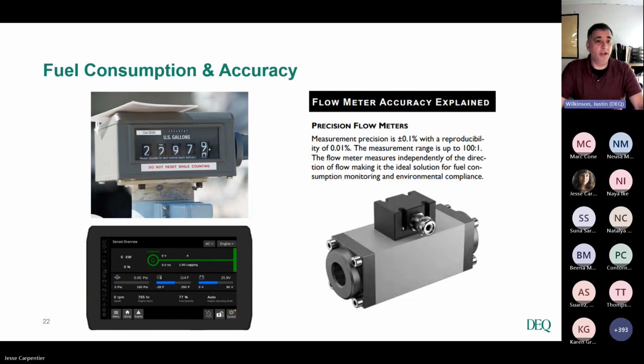When we started to apply that 5% to facilities, that was a huge amount of operation they were losing out on. So facilities started to look into external fuel flow monitors with higher accuracy to try to squeeze as much operation as they could out of those sites. We also started to see manufacturers coming around - they have a very large market here in Northern Virginia - so they started doing a bit more research, and we're starting to see better and better guarantees of accuracy for those ECMs.